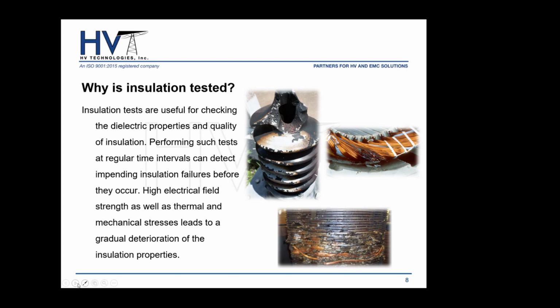Usually bushings and all these insulation systems are affected by the high electrical field strength, as well as thermal and mechanical stresses. That is what leads to the gradual deterioration of the insulation. And you get results sort of like what's pictured for a motor or a generator. You can have interwinding failures, winding insulation failures on bushings. You can have complete failure in a transformer. You can also have an example like this one where you have interwinding failures on your transformer.